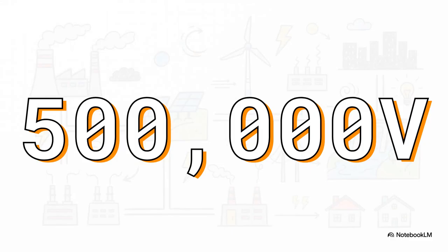And the reason I call it the heavy lifter is because of the sheer, almost unimaginable scale of its job. A traditional, massive generator usually creates power at somewhere between 15 to 23 kilovolts. But power just can't travel hundreds of miles across the country at that voltage without losing almost all of its energy to heat. So this main step-up transformer takes that 23 kilovolts and boosts it all the way up to 220 or even 500,000 volts. It is at this massive 500 kilovolt level that the power is finally injected into the national transmission grid to make the long journey to your city.